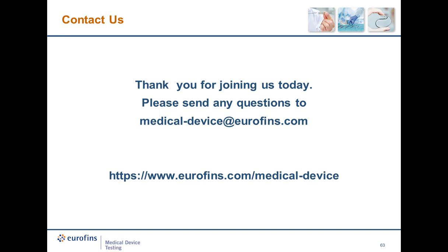Thank you. Next question for Matt. Are E&L tests required for all types of devices? Thank you. There are definitely devices out there that are not appropriate for chemical characterization. There was a slide in my part of the presentation that talked about the different classes of medical devices and how typically only class 2 and class 3 devices are applicable for chemical characterization. Really, the risk assessment is the big factor here.